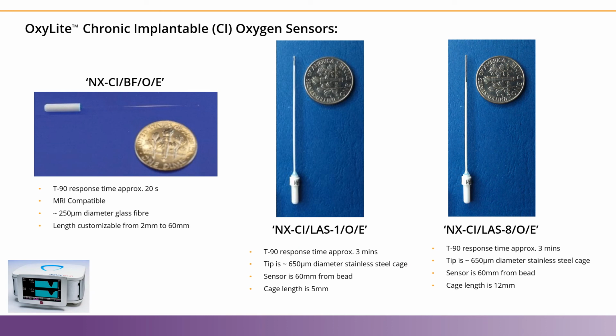So let's take a look at the three different types. First, we have the bare fiber CI sensor, which consists of a thin 250 micron glass fiber. Since it's flexible and fragile, this sensor must be introduced into the tissue with a catheter or cannula. When these sensors are ordered, you can order them at a custom length anywhere between 2 millimeters and 60 millimeters. Later in the video, I'll show you a comparison between the two different lengths for this sensor.